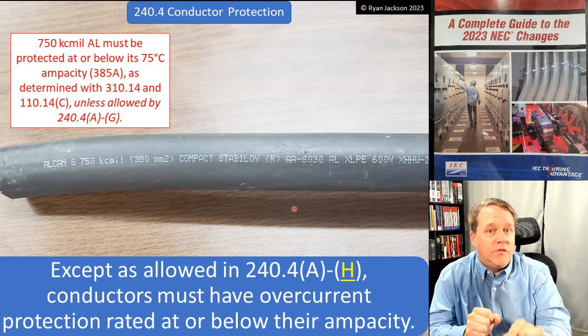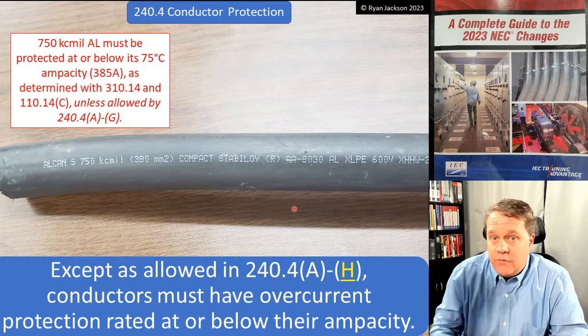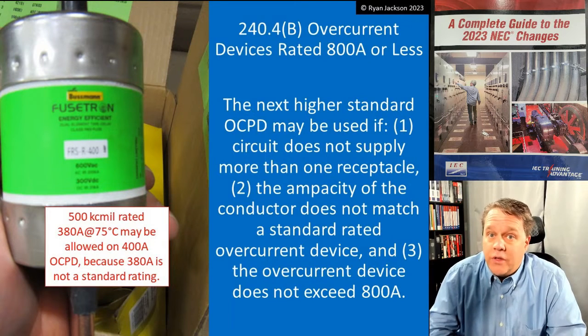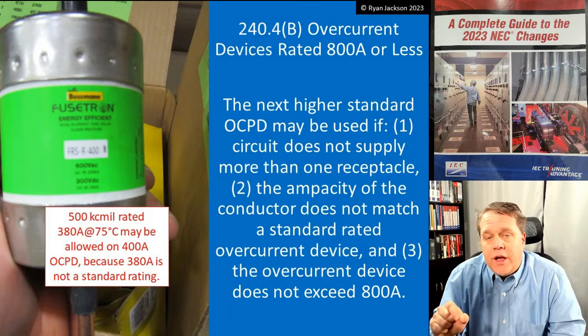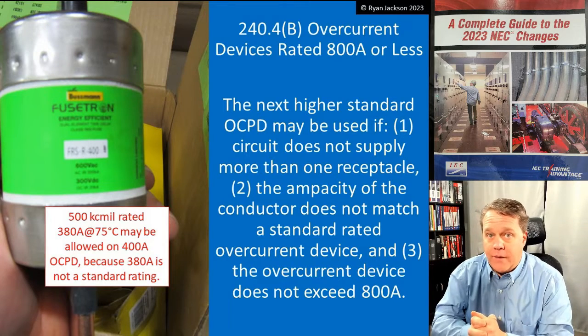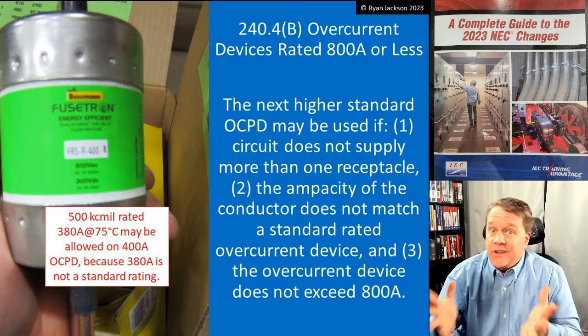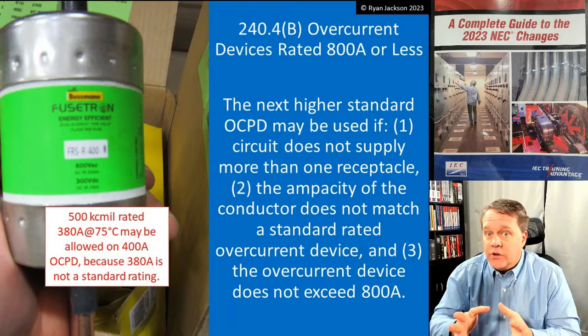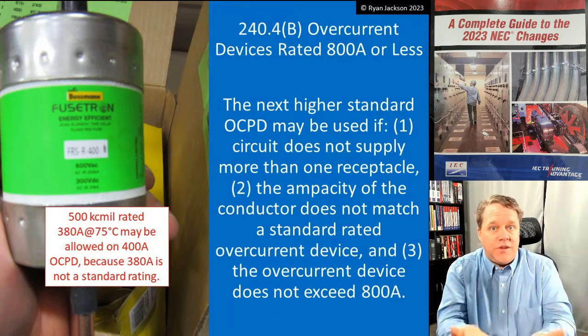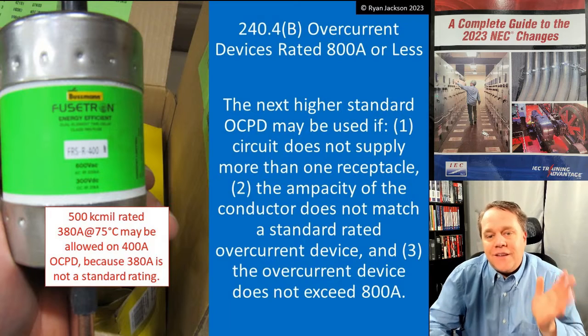This rule means you can put a maximum 385-amp breaker or fuse to protect this 385-amp wire, except as allowed in (A) through (H). Now, 240.4(B) is probably the rule you need to know more than any other — it covers overcurrent devices rated 800 amps and less. How often are you putting in breakers or fuses larger than 800 amps? Seriously, 99% of the breakers and fuses you install are 800 amps or less, so this is the rule for 99% of your work.